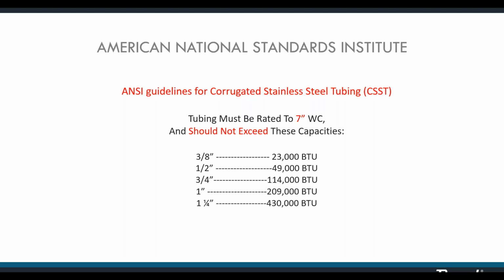Let me show you what I'm talking about. ANSI standards indicate what sizes of corrugated steel tubing you can use. Most people, again, just use the 3/4 inch, okay? But 3/4 inch is only going to accommodate up to 114,000 BTUs. Okay, we don't even make a gas burning heater that small. So now you could upgrade up to that 1.25 inch. That would accommodate up to 430,000 BTUs. That'll cover this appliance.